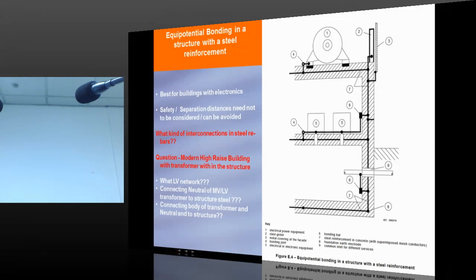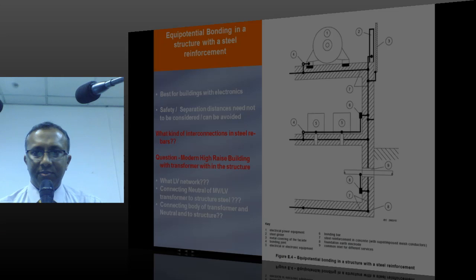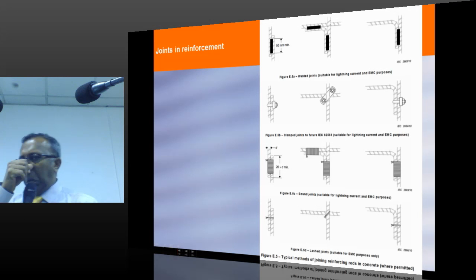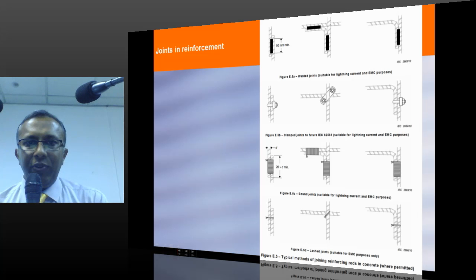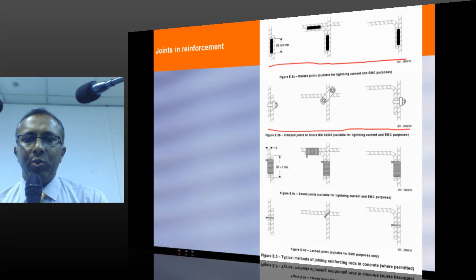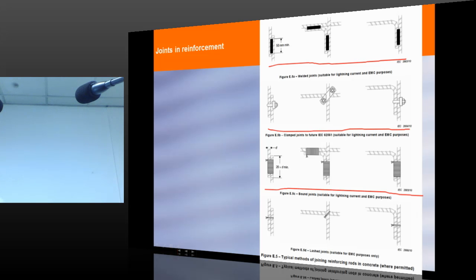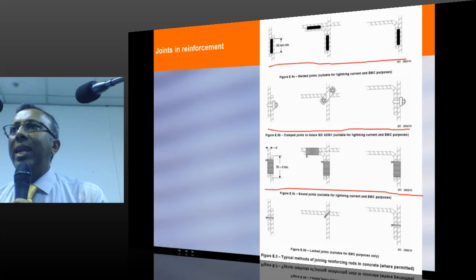I hope you understood. Basically, to achieve good protection for a modern building, you need to connect steel reinforcement. You need to use steel reinforcement as a part of the lightning protection system, under these conditions. So, as I explained to you, every 5 meters you have to have a strong connection. These are the conditions, the first three lines, 1, 2, 3. These are the things ensured in the standard, which is supposed to handle partial lightning current.